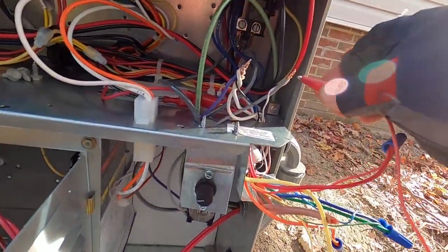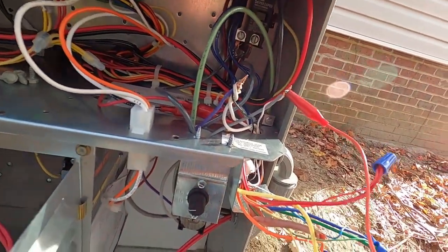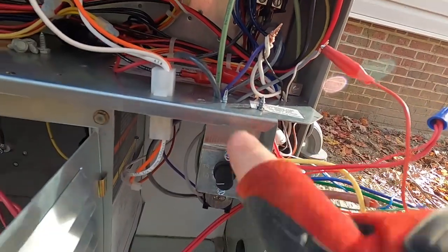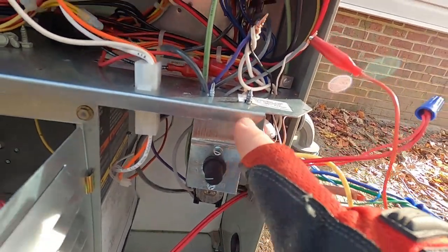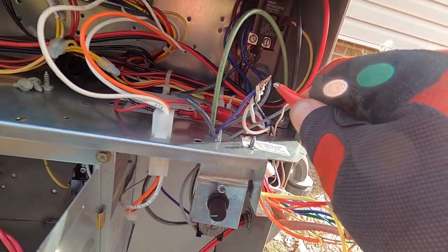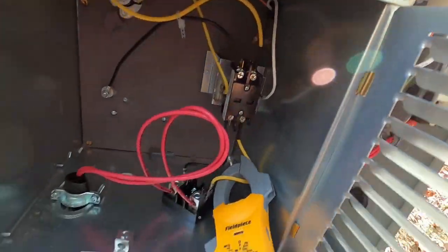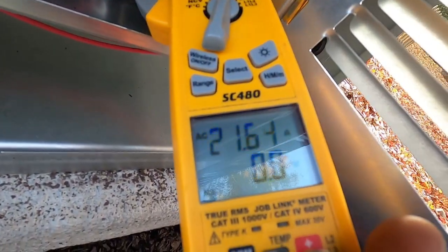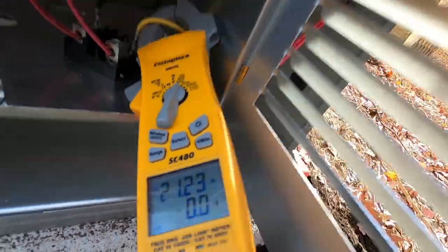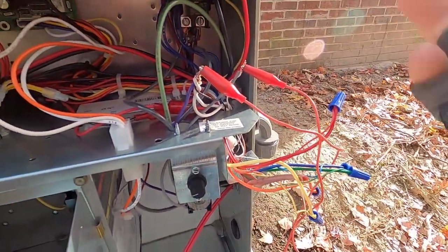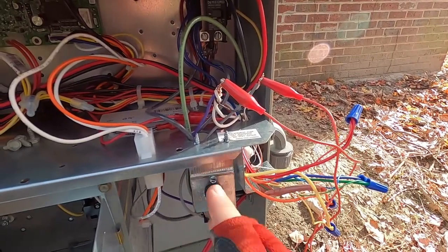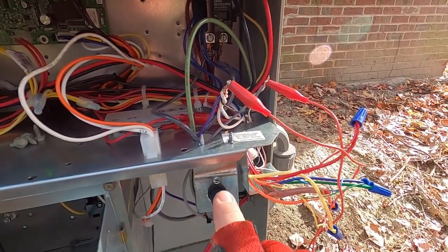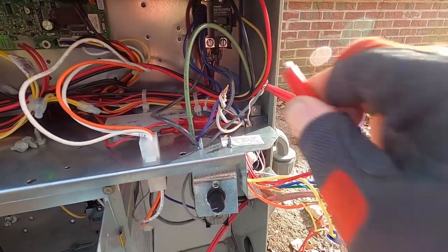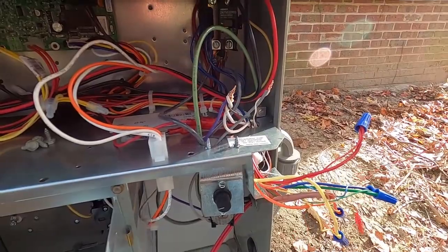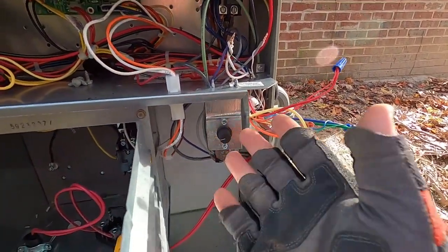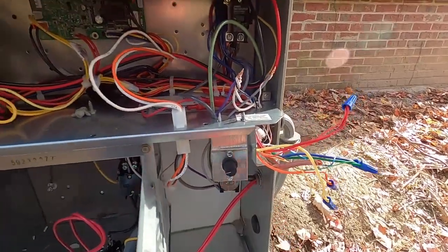So I know my thermostat's calling. I'm simply just going to jump across the inside, the end of that switch to the out, which comes back when that switch closes, turns on the heat strips. You just heard the contactor close, and we have 21 amps on our heat strips. So I know now if the auxiliary circuit initiates at the thermostat, this switch is closed, the temperature is below our set point for the switch, it will pass voltage through and turn on the heat strips, assuming the switch closes. They usually do. These things don't go bad. You just got to have the right one, like I said.